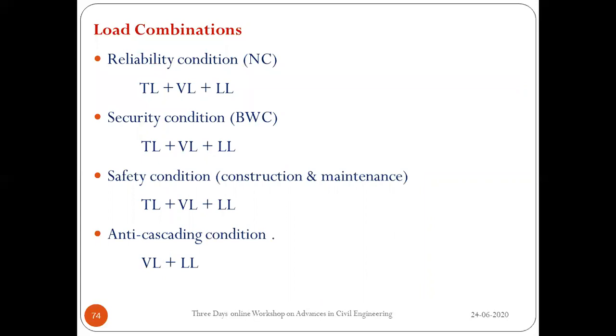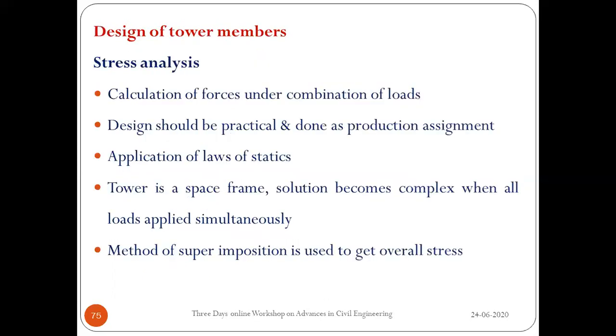Load combinations for design: for reliability conditions, vertical, transverse, and longitudinal loads act simultaneously. For anti-cascading conditions, no transverse load is considered — only vertical and longitudinal loads. Once load calculations are complete, the tower is analyzed using software to obtain maximum axial compression and tension for member design.